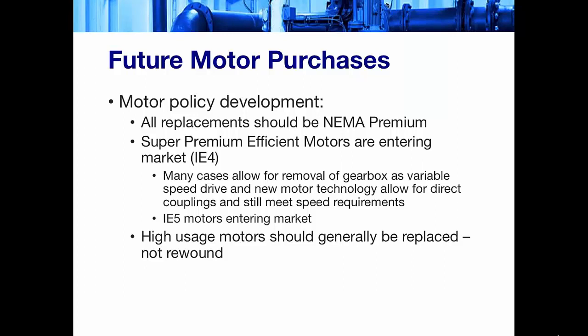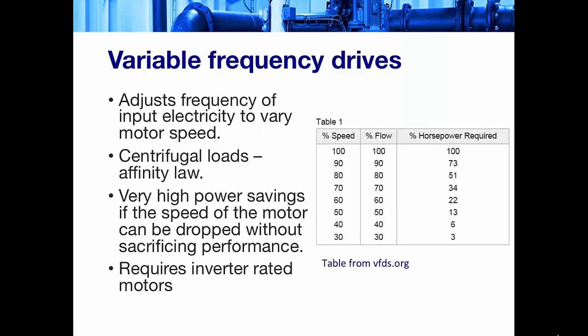On the subject of variable frequency drives, on the next slide, there's a table on the right side. Basically, variable frequency drives change the frequency of the incoming electricity, slowing the motor down. For centrifugal loads, which most water pumps are, and most aeration blowers are also centrifugal loads, there's something called the affinity law, where the horsepower required is related to the cube of the speed. So if you can slow it down, you can have linear proportional drops in flow and much higher than linear proportional drops in horsepower. Going from 100% speed to 80% speed will get you about 80% flow on a centrifugal load, but will only require 51% of the horsepower.